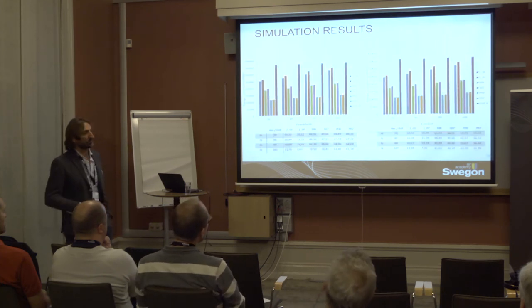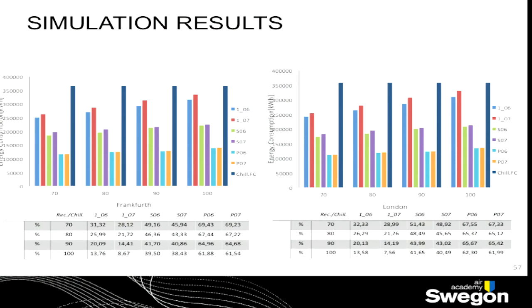And these are the results. We considered 4 different situations. This is the pressure losses for every one of the heat exchangers inside of the system. So every one of them loses 70 pascals in this situation, 80, 90, and 100. What does it mean? It means that if I've got 2 plate heat exchangers, I'm losing 200 pascals. And we made this comparison with a single, with a series, with a parallel, and with a chiller free cooling system, the first one that we considered before.